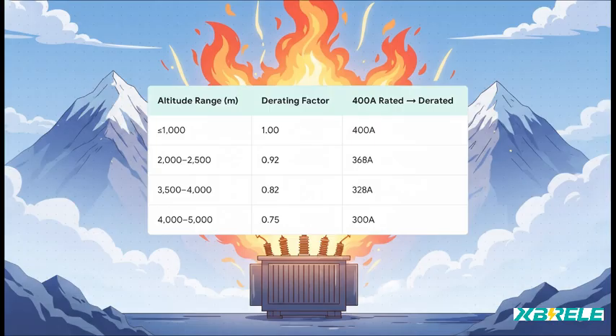All right, now for that second problem, heat. Since thin air is so bad at carrying heat away, engineers have to do something called derating the equipment—that just means they intentionally run it at a lower current to keep it from overheating. For example, a device rated for 400 amps can only be safely run at 328 amps once you get up to around 3,500 or 4,000 meters.